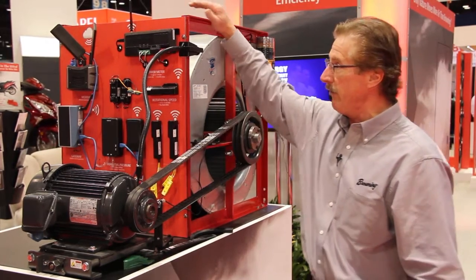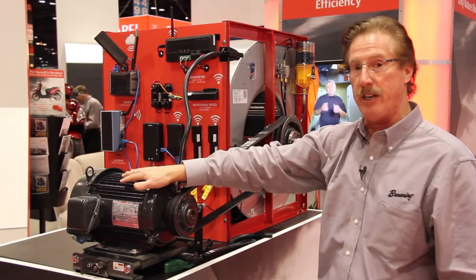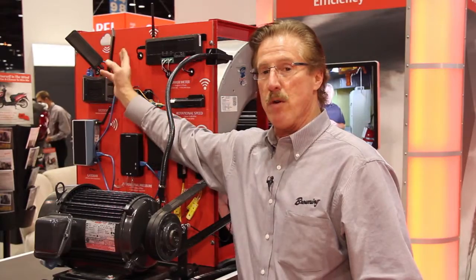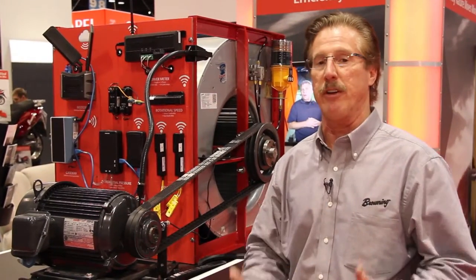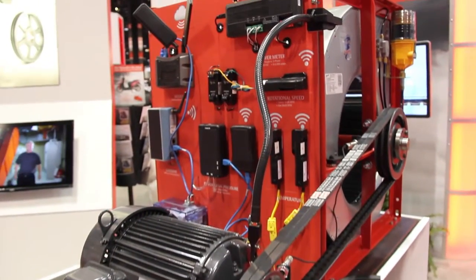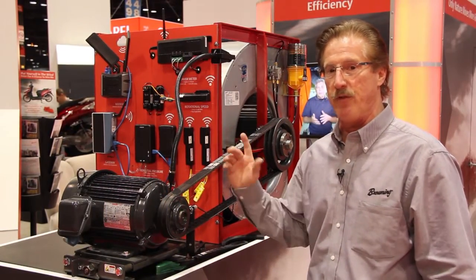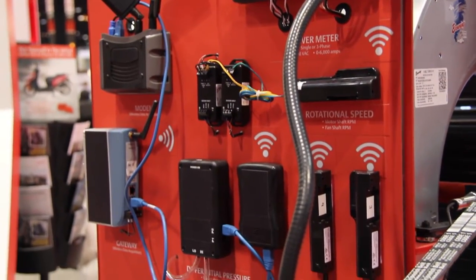the green. So we have developed an energy monitor wireless platform that measures the energy consumption through the motor over time and can transmit that to a gateway that through a modem can then send the information to a laptop, so that you can actually see how much energy degradation you're getting over time. And again, because the blowers in a building are typically the number 2 draw on the energy consumption of a building behind lighting, it's very important to make sure they're running at peak performance. And this monitoring system allows you to do that.